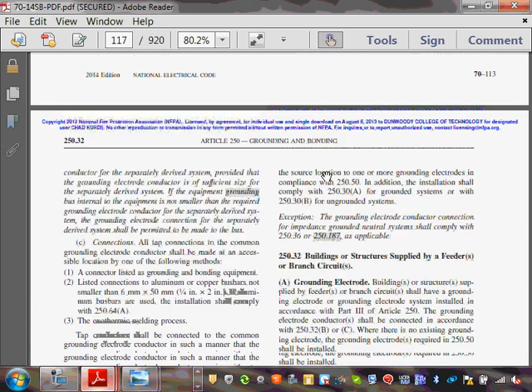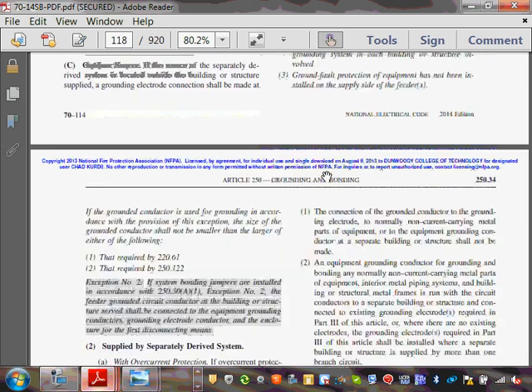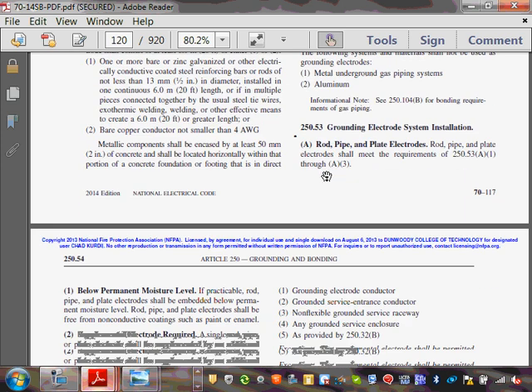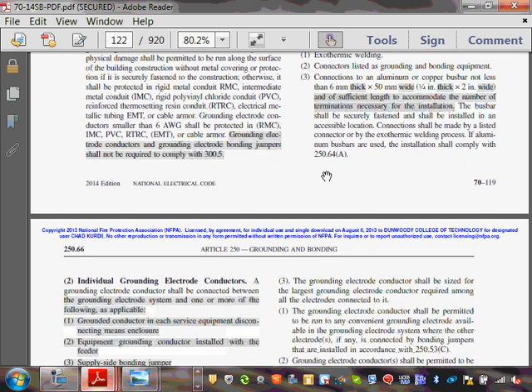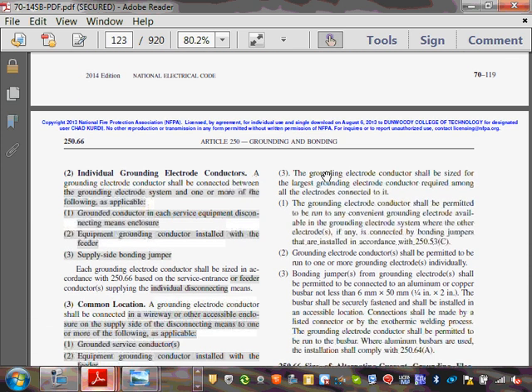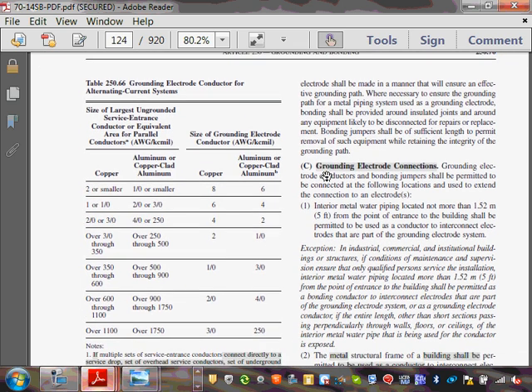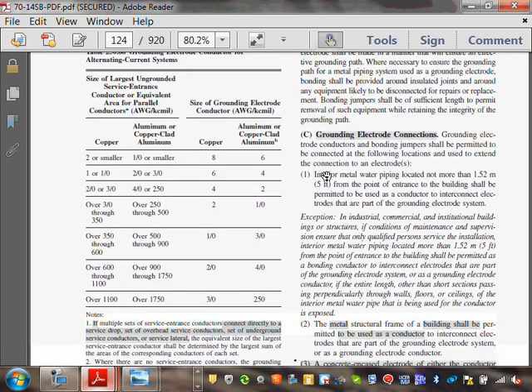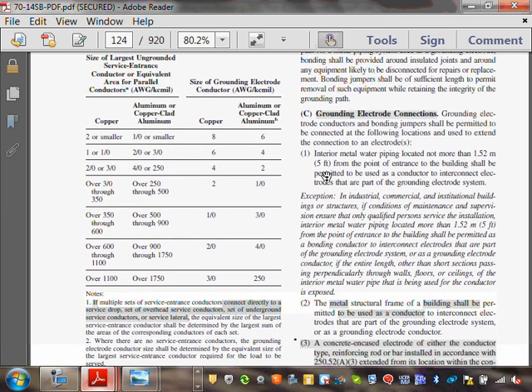Where are we here? 250.66. Okay. Did you guys recognize this table? This is your 250.66. Can you guys look at it if you have a book? It says grounding electrode conductor for alternating current, and it's only to be used for grounding electrode conductor. The same table that you use is for grounding electrode conductor, that 250.66. And it talks about if you parallel, how to size it.